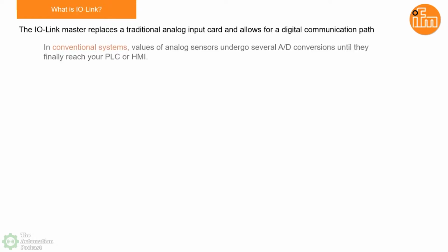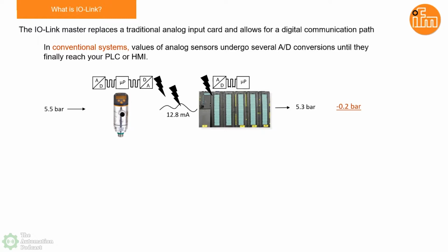One of the best use cases for IO-Link is its ability to replace anything analog with a digital communication path. Taking the pressure sensor example I showed before, with conventional analog wiring we send the signal via traditional analog wiring back to the PLC. You can see in this diagram that multiple A/D conversions are needed in order to get back to the PLC.